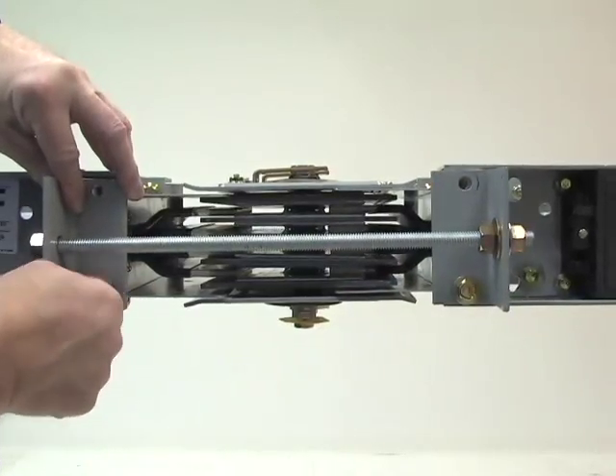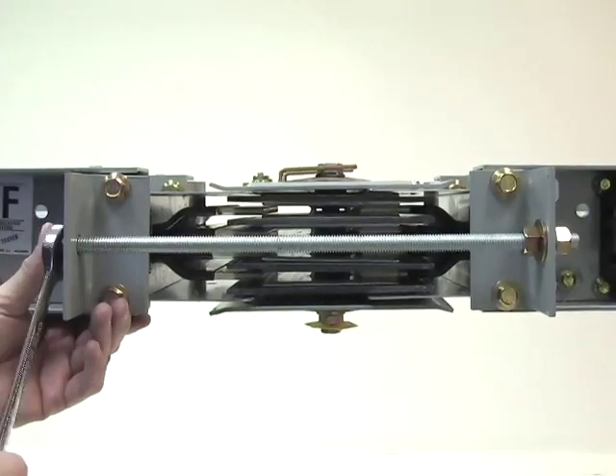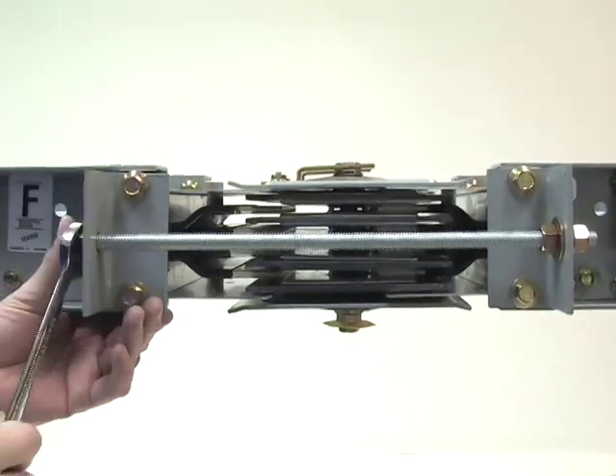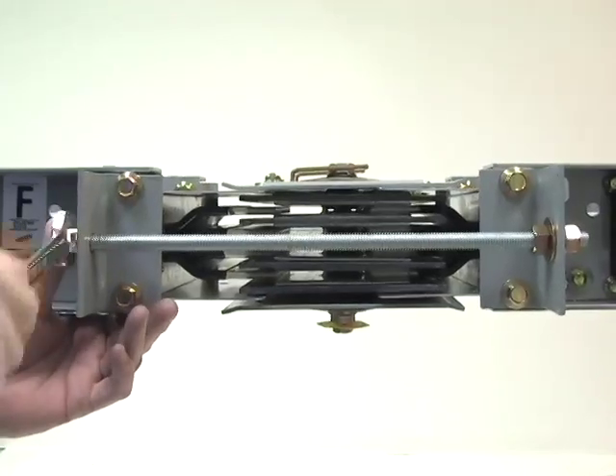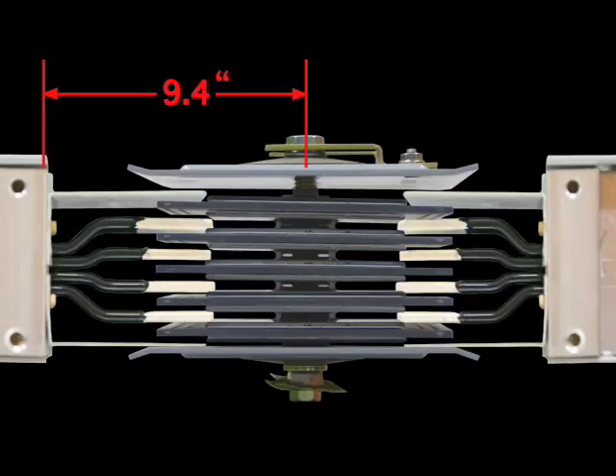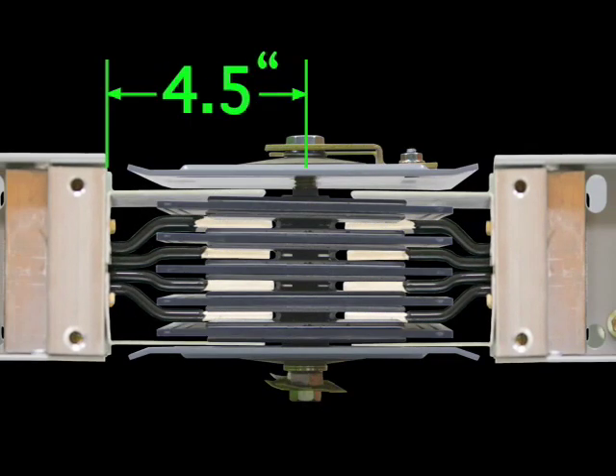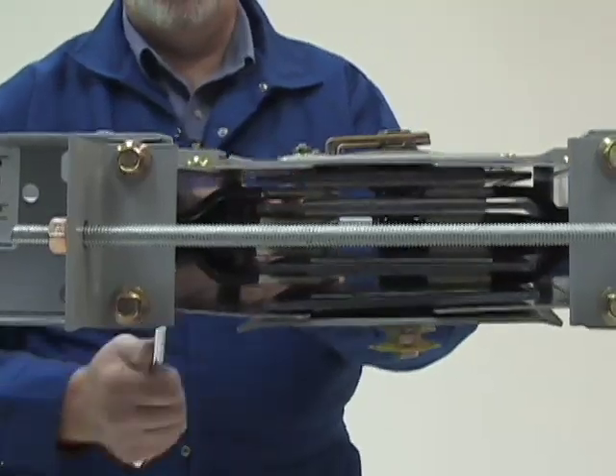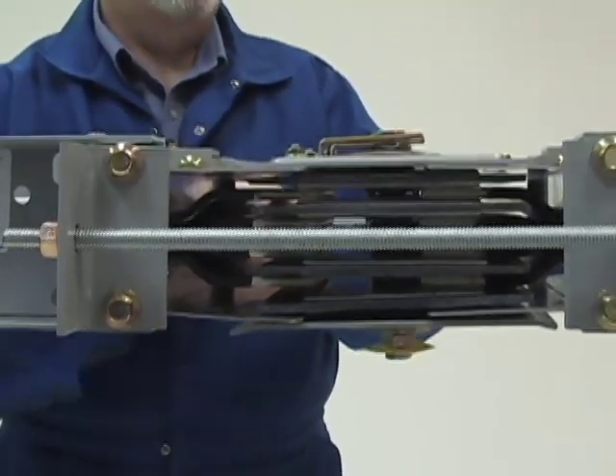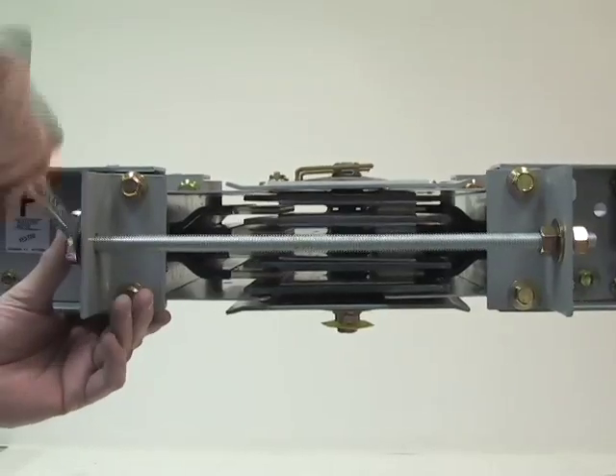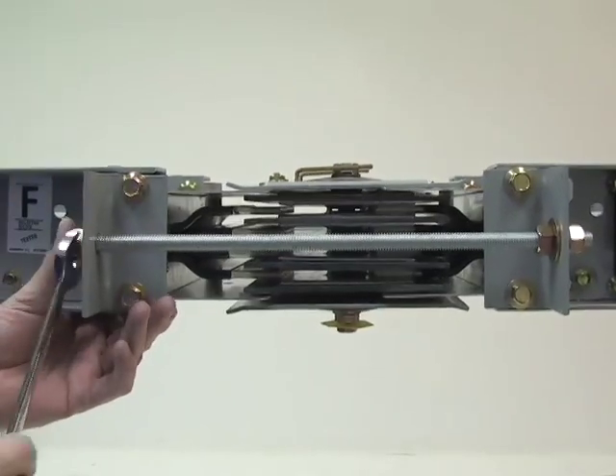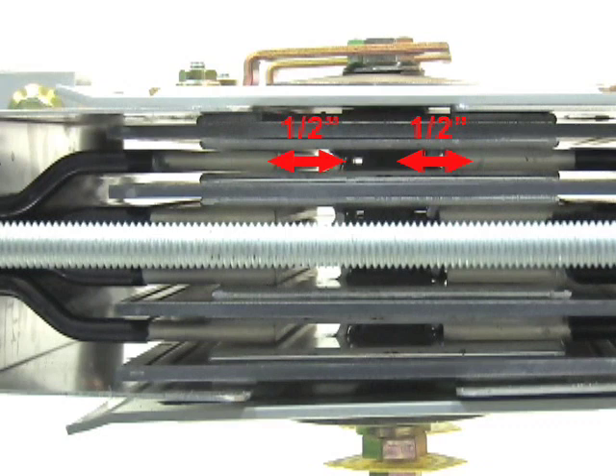Continue pulling the busway together by tightening the nut on the joint puller bracket until the distance from the edge of each housing to the center line of the joint bolt is approximately 9.4 inches. You should alternate tightening the joint puller assembly nuts to each side of the busway to ensure that the joint is pulled together squarely. Power bridge joints are adjustable 1/2 inch in either direction.